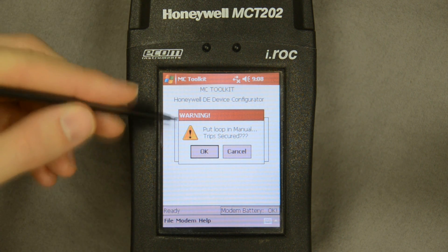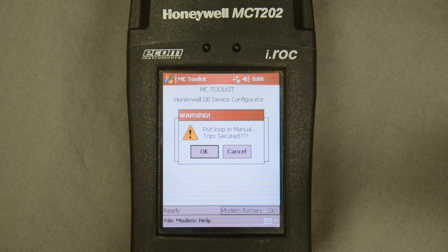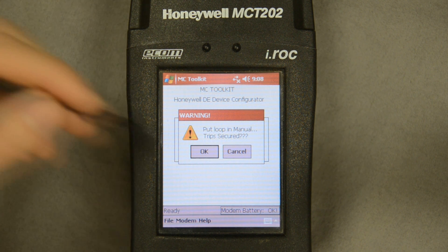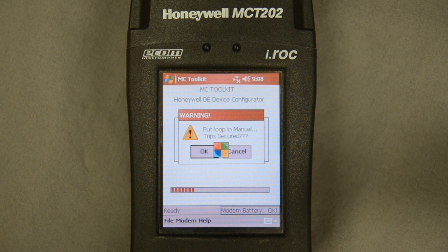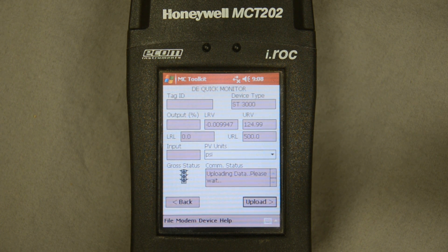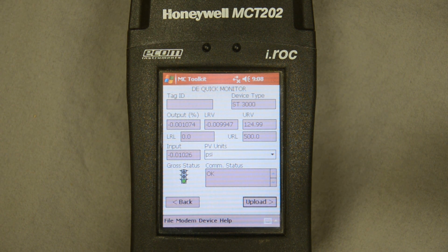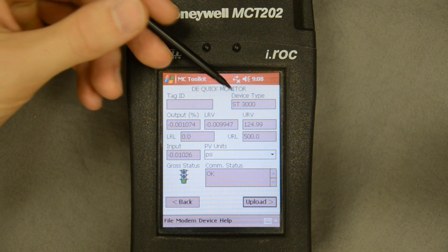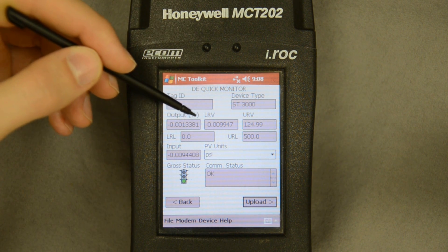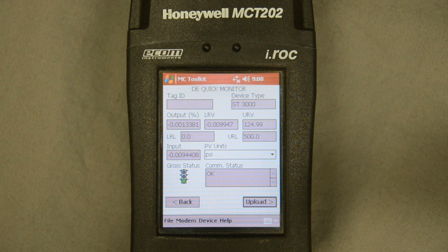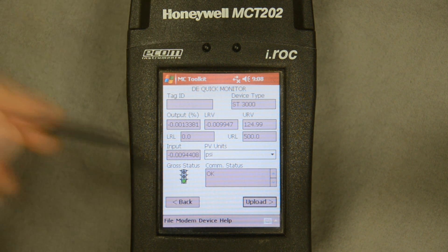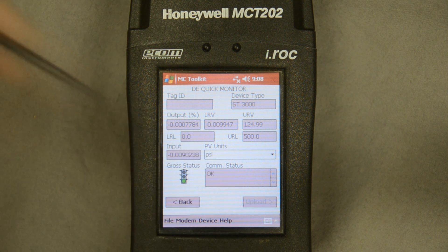I get the same kind of message as with the HART device, reminding me that I can create process upsets by communicating with a transmitter that's actually in service. I'll plow through that and it starts pulling up the device information digitally into the program. The first screen I get is a status screen, which basically gives me the front page of the transmitter — the tag information, the type (in this case an ST3000), the lower and upper range values, and a green status confirming everything is okay with this transmitter.